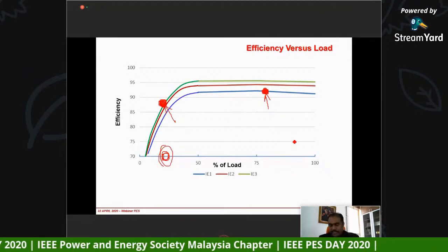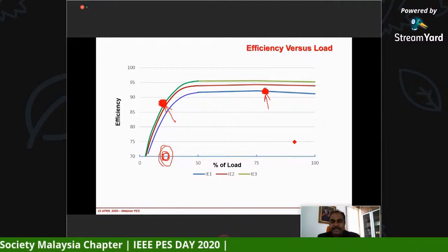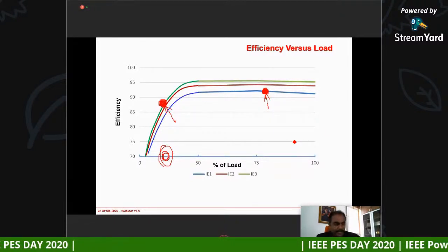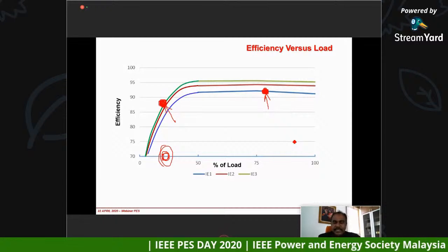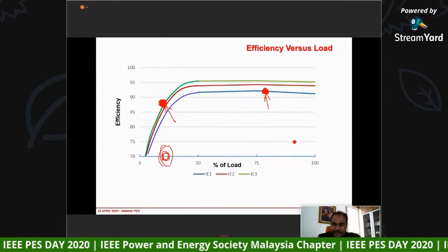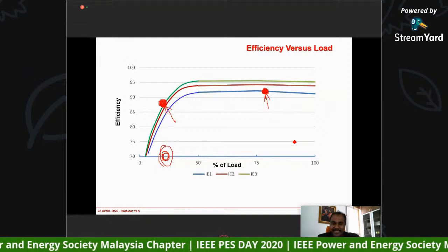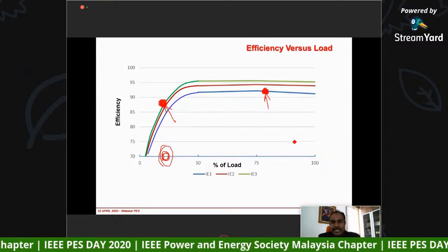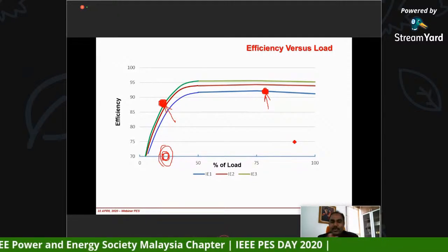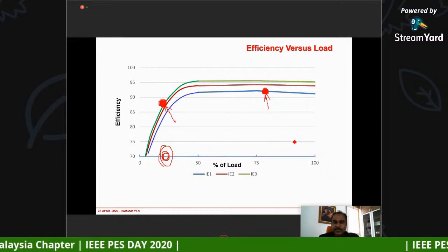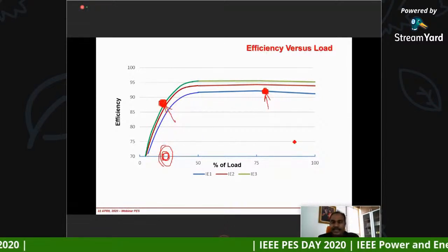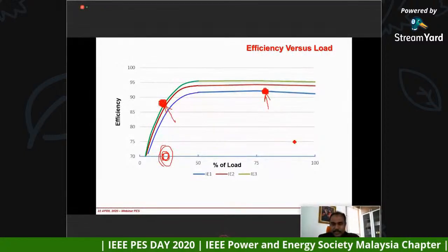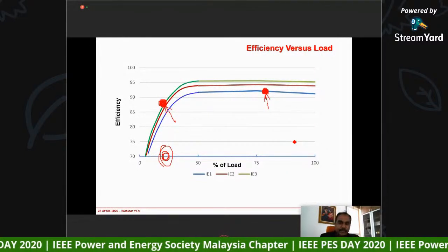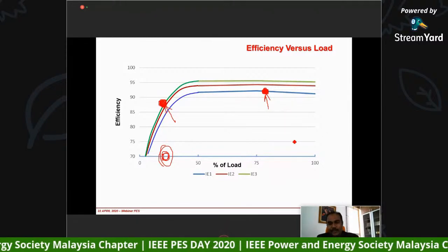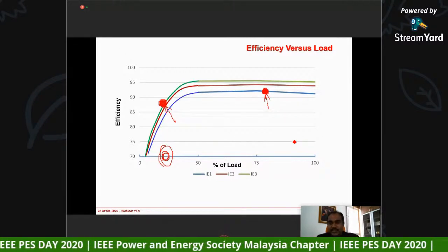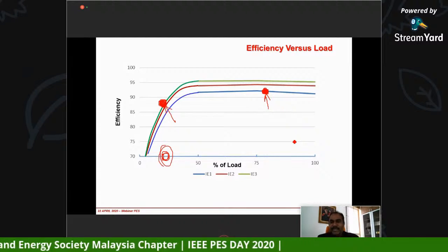Correct. So this is possible, and it always happens in industry, because most of the time when we go into the industry, the engineers are not aware of the loading factor of the motor at the moment. All the while they see the motor is running fine, but they are not sure what the loading factor is, whether the motor is driving 75%, whether the motor is driving 50% load. They have no idea about it. So when you don't have that idea, if you just blindly convert to an IE2 or IE3, you notice that you don't see so much saving, or probably no saving at all.